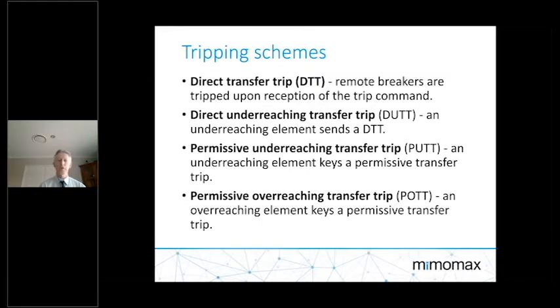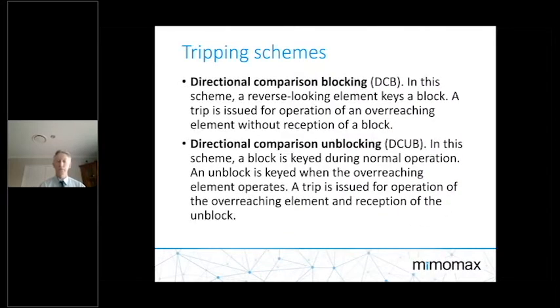So it kind of depends on where in the network we are looking to source the data and actuate the relay. And also we have comparison blocking and directional comparison unblocking. So this is where the trip is used for an operation of an overreaching element without reception of the block, and this directional comparison unblocking is where the block is keyed during normal operation, and the unblock is keyed when the overreaching element operates. So different numbers of schemes or different types of schemes that are used in different applications, and all kind of wrap into the teleprotection requirements depending on where you are operating in the network.